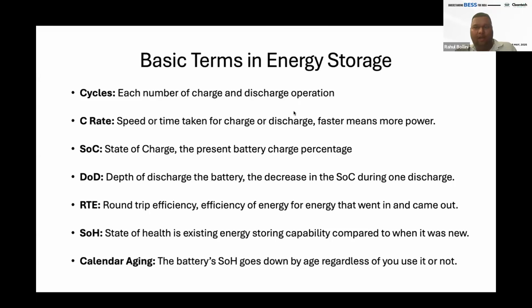Then RTE is a very complicated and very important factor of why BESS, and why LFP or lithium-ion battery, is a clear winner most of the time - that's because of round trip efficiency. Typically the 314 Ah cells used today have about 95-ish percentage. At a system level, if it's 4 hours you get about 94 plus, and if it's 2 hours you get slightly lower than 94% on day one. And this RTE goes down - we'll talk about that in a minute.